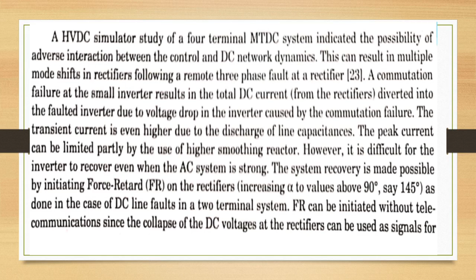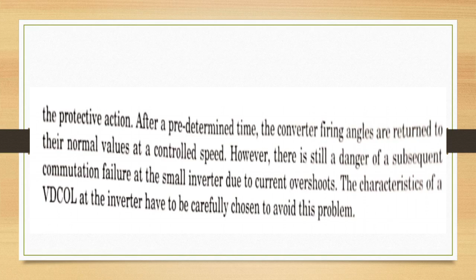FR can be initiated without telecommunications since the collapse of the DC voltage at the rectifier can be used as signals for the protective action. After a predetermined time, converter firing angles are returned to their normal values at a controlled speed. However, there is still a danger of a subsequent commutation failure at the small inverter due to current overshoots. Characteristics of VDCOL at the inverter have to be carefully chosen to avoid this problem.